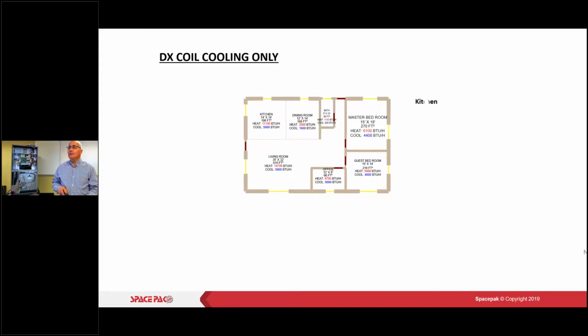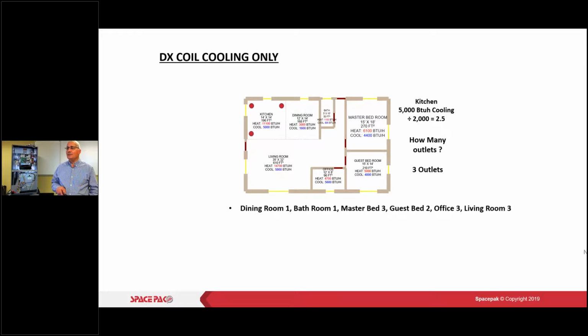So what would that look like if we were cooling only? Start filling in the blanks here. There we go. So I need 5,000 in the kitchen. We divide that by 2,000 BTUs, it's 2.5 outlets, so that's going to be 3. Dining gets 1, bath gets 1, master bed 3, and so on and so forth. You can see that based on our load calculations, where the outlets are going to be.